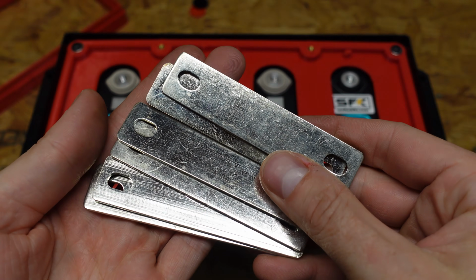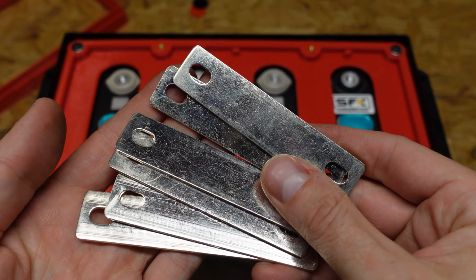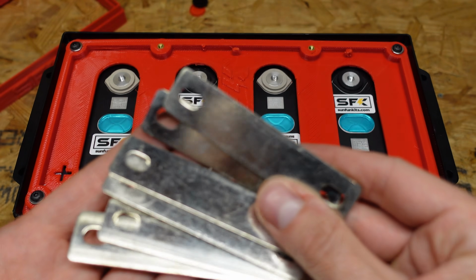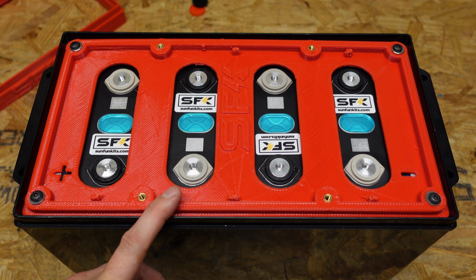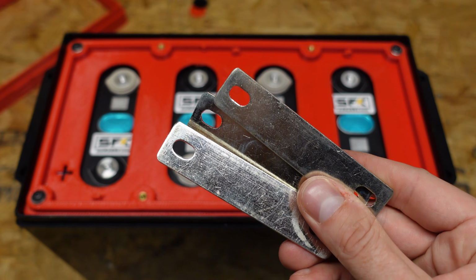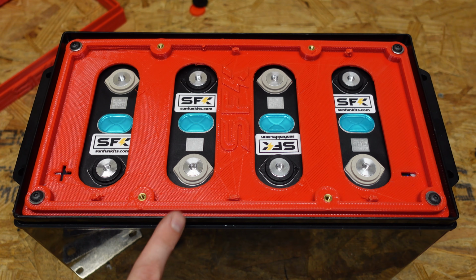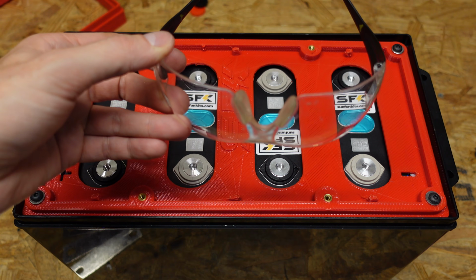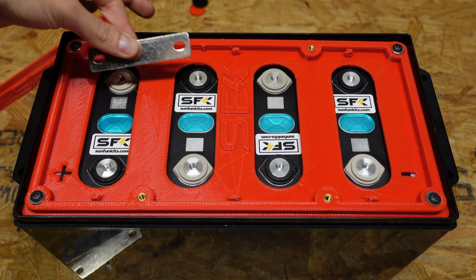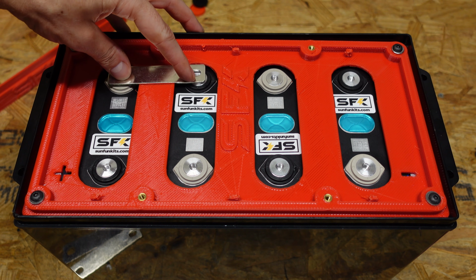So next we're ready to install our bus bars. We do have extra bus bars here because these are intended to be used for the parallel connections if you're top balancing. We will only need 3 bus bars for this. Anytime you do something like this, you definitely want a pair of safety glasses. And I'm going to very carefully set the bus bars in place.